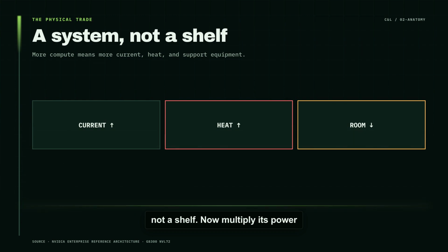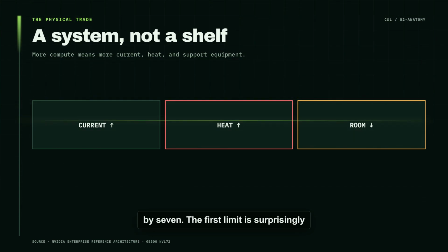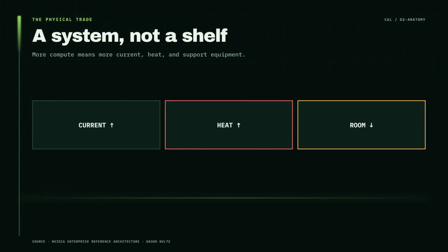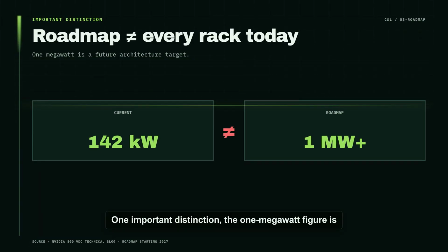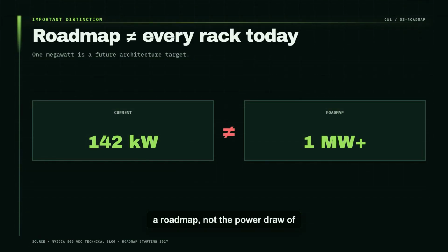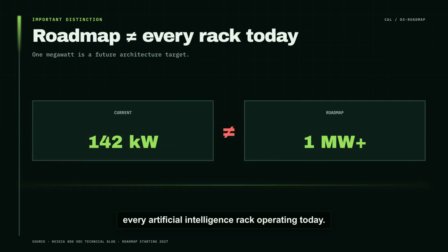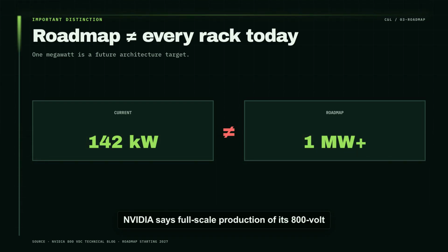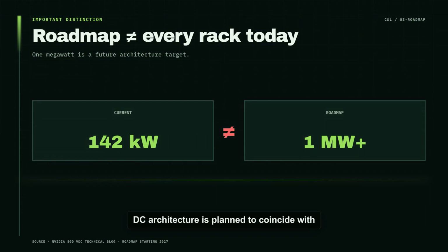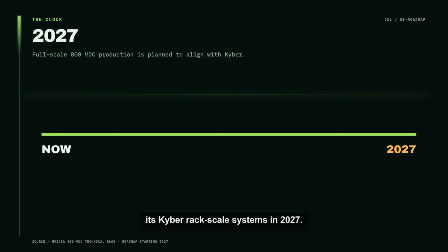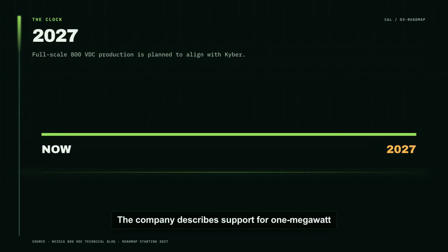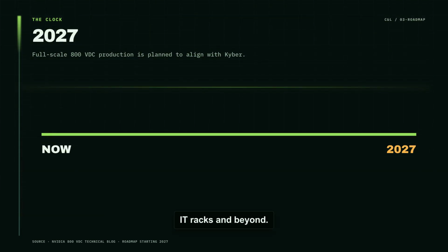Now multiply its power by 7. The first limit is surprisingly simple. There may be nowhere left to put the power supplies. One important distinction: the 1 megawatt figure is a roadmap, not the power draw of every artificial intelligence rack operating today. NVIDIA says full-scale production of its 800-volt DC architecture is planned to coincide with its Kyber rack-scale systems in 2027. The company describes support for 1 megawatt IT racks and beyond.